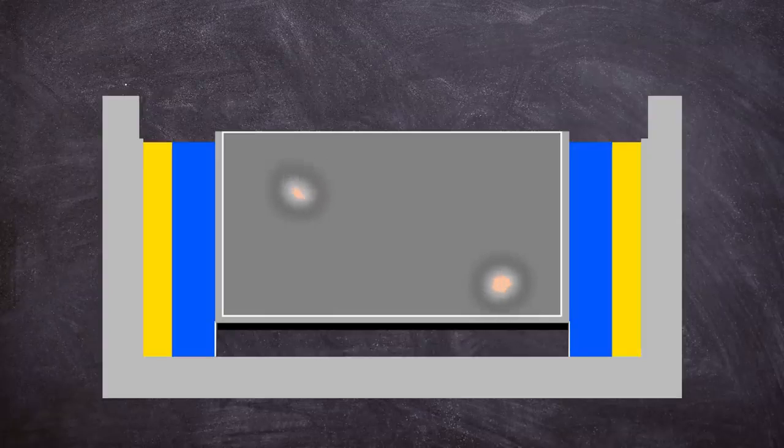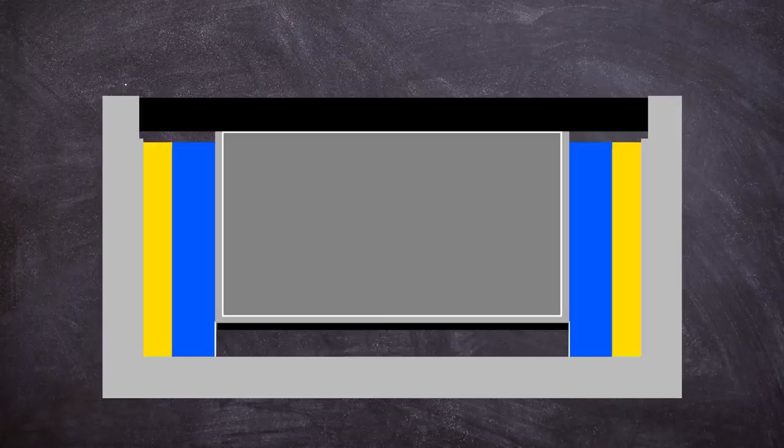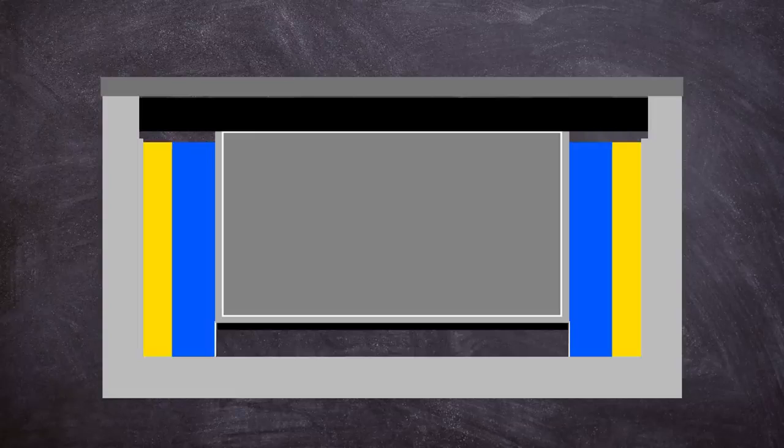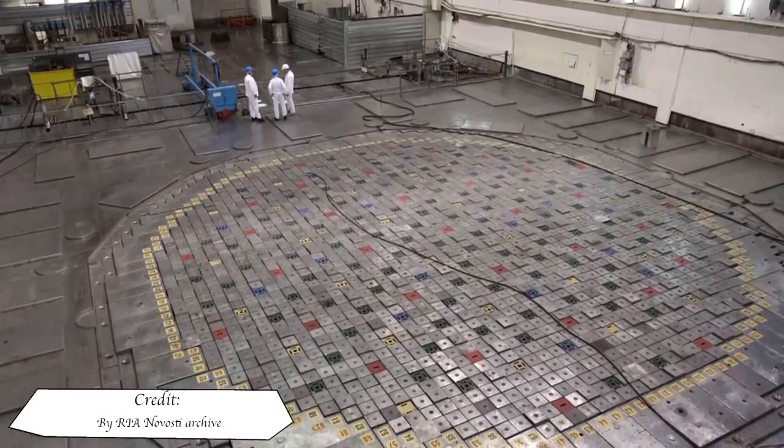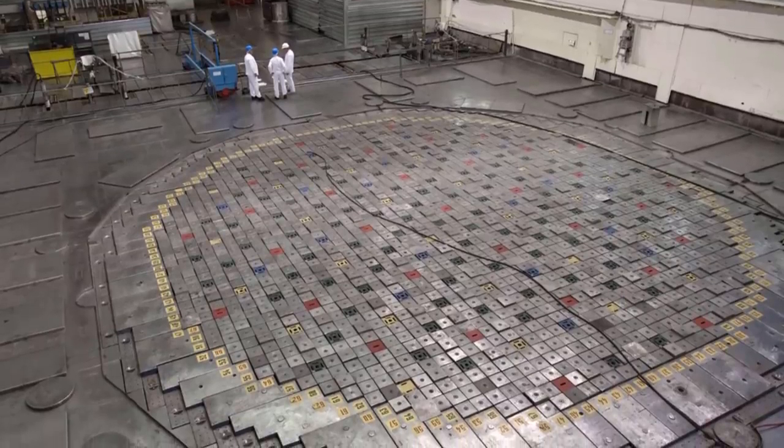The core consisted of graphite blocks sized 25 by 25 centimeters stacked up with holes drilled through the center for fuel and control channels. The size of the core could cause issues in reactivity control during operation but we will talk about that a bit later on. On top of the core another biological shield was placed with a steel cover on top of it which formed the floor of the reactor hall. The cover plate was capable of withstanding a pressure buildup resulting from steam released by two simultaneous channel ruptures. All of this allowed the design to be refueled whilst in operation which again helped with costs by reducing downtime.